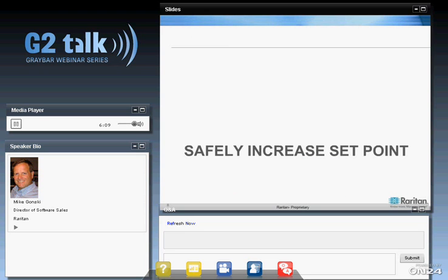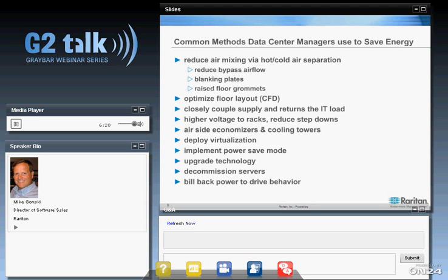The first area we look at for savings with DCIM is safely increasing the set point within the data center. There are many common methods data center managers use to save energy: blanking panels, bypass airflow, raised floor treatments, and the big trend toward virtualization, which was very successful for cost savings. We're also seeing people interested in savings from delivering high power to the rack — some are delivering 400 volts directly to the rack. DCIM systems can also help with decommissioning servers and identifying ghost servers from power data.